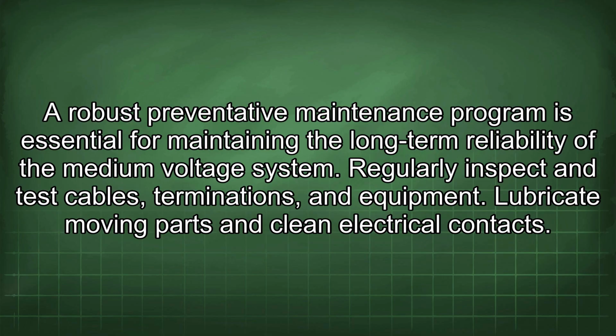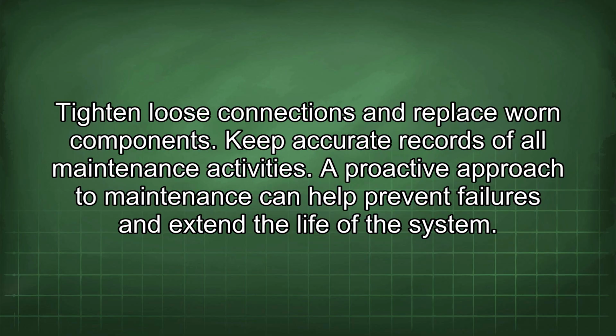A robust preventative maintenance program is essential for maintaining the long-term reliability of the medium voltage system. Regularly inspect and test cables, terminations, and equipment. Lubricate moving parts and clean electrical contacts. Tighten loose connections and replace worn components. Keep accurate records of all maintenance activities. A proactive approach to maintenance can help prevent failures and extend the life of the system.